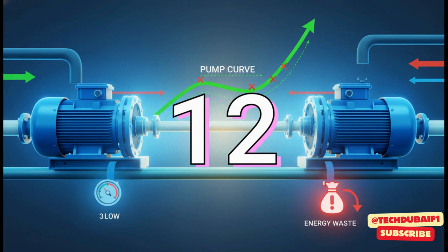A total of 12 of these pumps across the 4 zones are put through their paces. Testers are checking to see if they're operating on their pump curve.